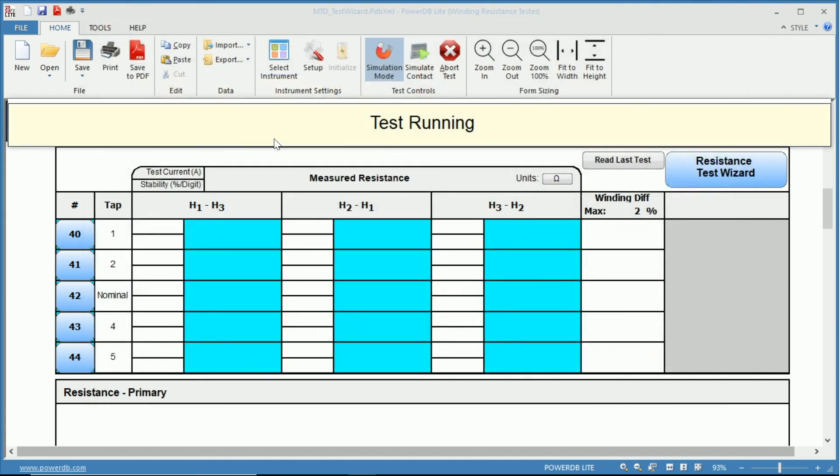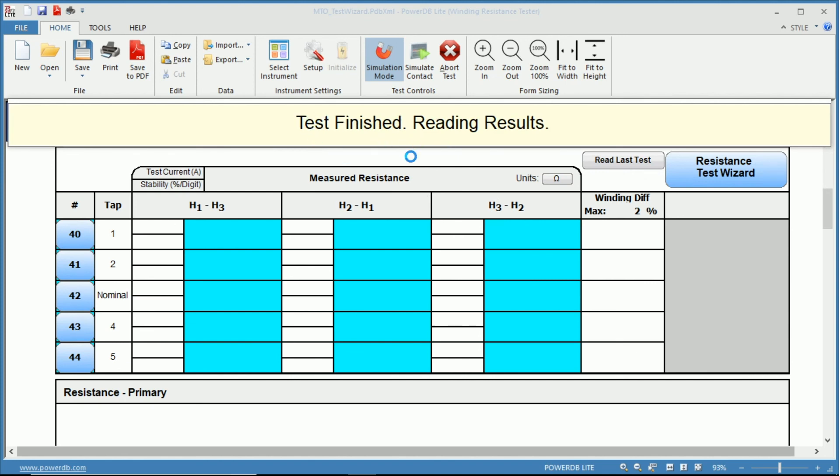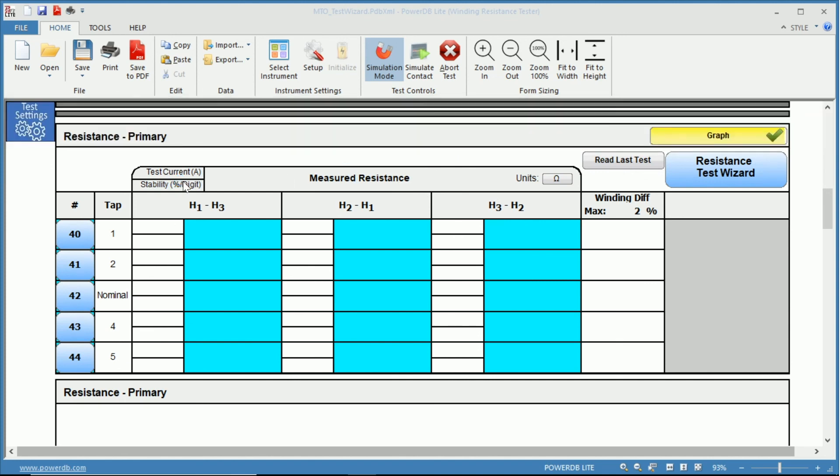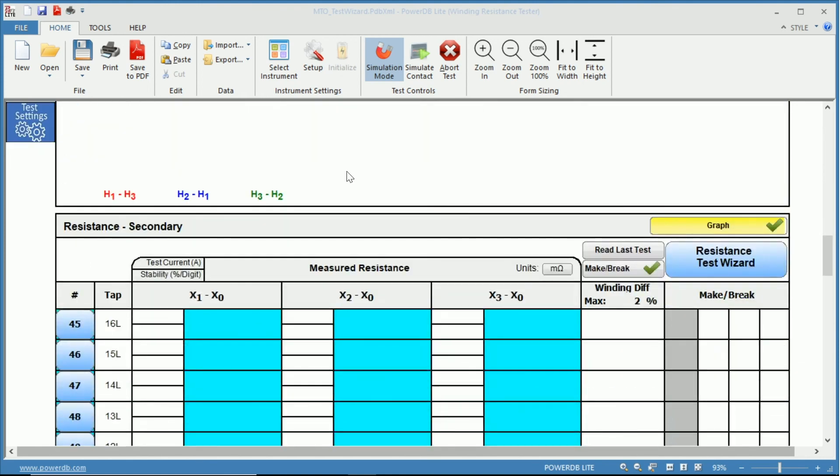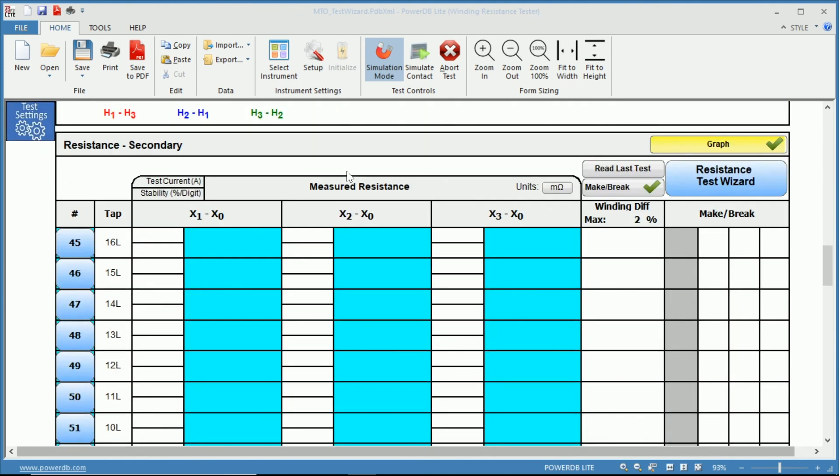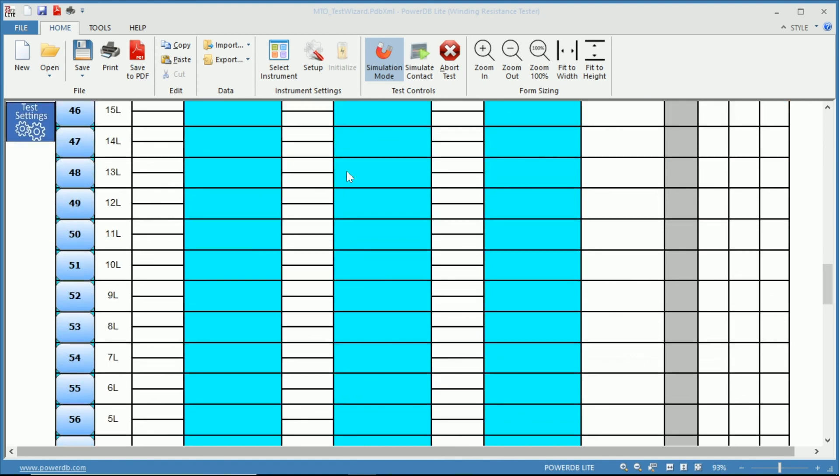And now it's measuring the resistance of your tap one raise. Once completed, you can notice it did discharge the phase. Now it's saving the results, and we have the test finished, and we can read our results.